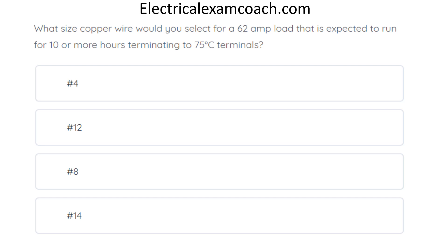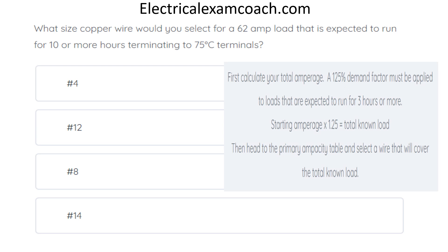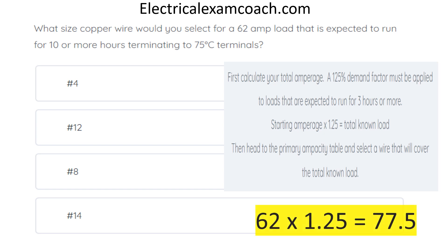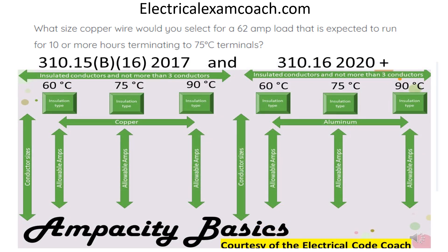What size copper wire would you select for a 62-amp load that's expected to run for 10 or more hours, terminating to 75-degree C terminals? The correct answer is number four. When calculating your total amperage, you must apply a 125% demand factor for all loads expected to run for three or more hours. Take your starting amperage multiplied by 1.25 to get your total known load — 62 amps times 1.25 equals 77.5 amps. Head to the primary ampacity table on the copper side, use the 75-degree C column, find a wire that covers 77.5 amps, and tee off to find your conductor size.